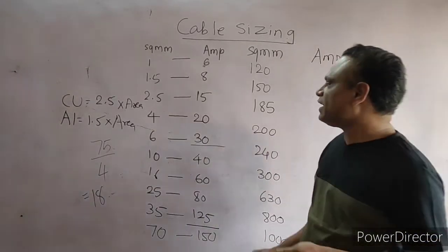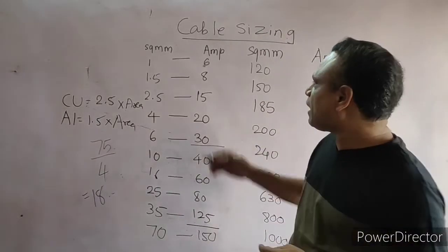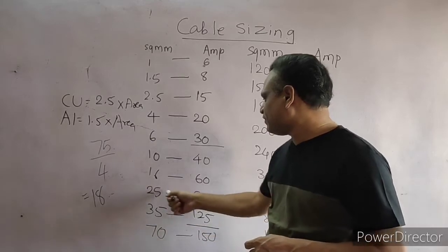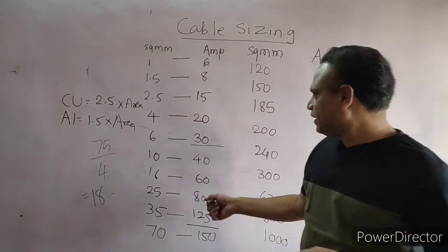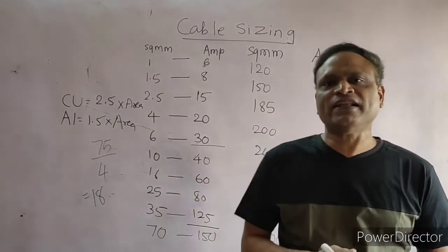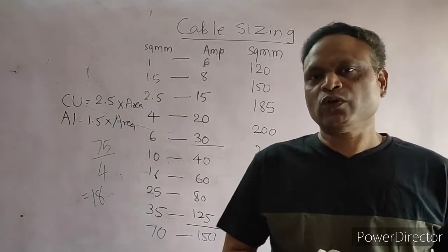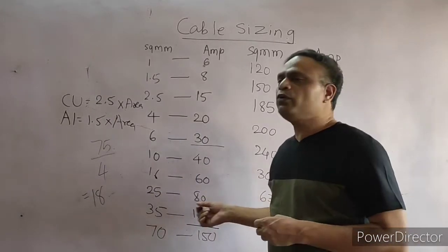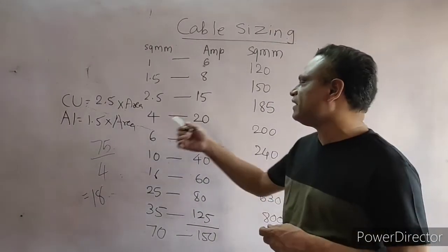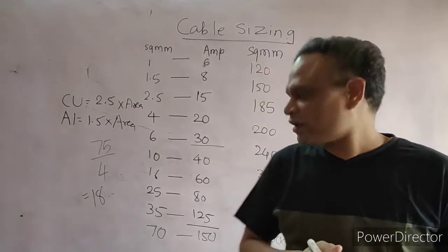But this is actually a calculation with a rough estimation because we have not considered the derating factor. Now for 75 amperes, if this cable is selected, 80 is multiplied by 0.8, since generally the derating factor is up to 0.8 in the worst condition. So 80 into 0.8 will be 64 amperes. But my current is 75 amperes. Hence, it is not suitable for that application.